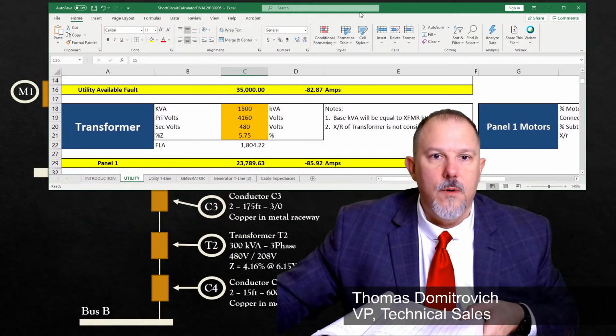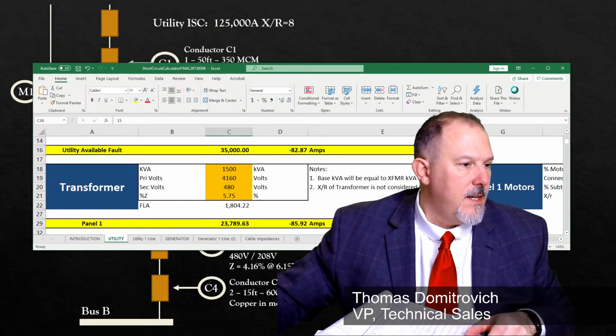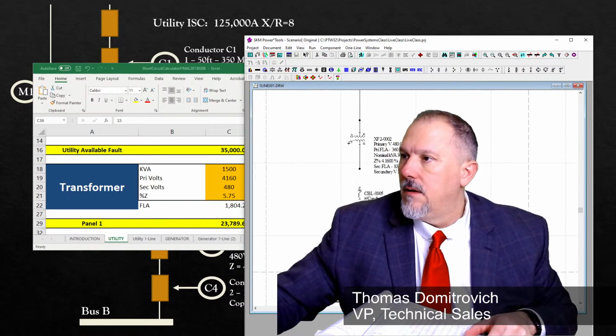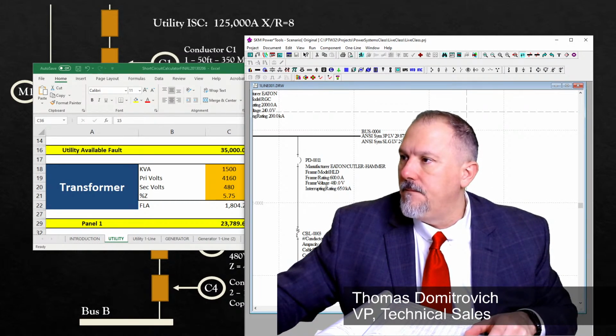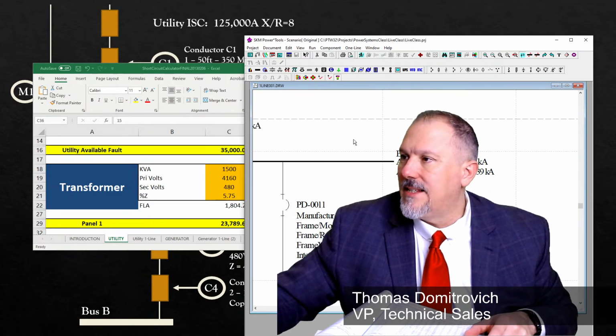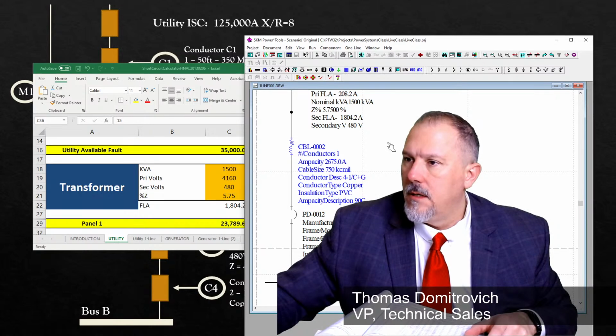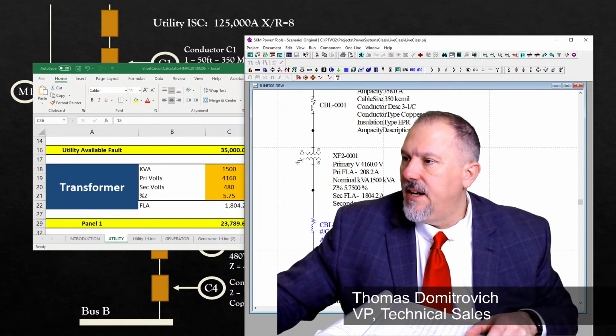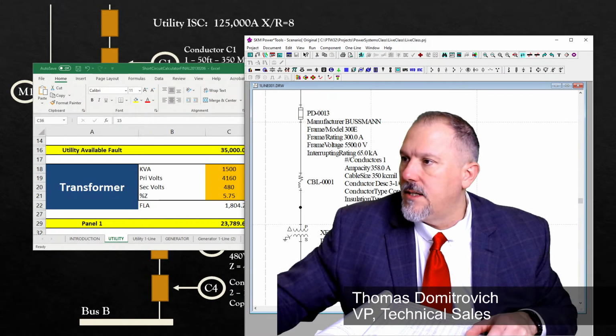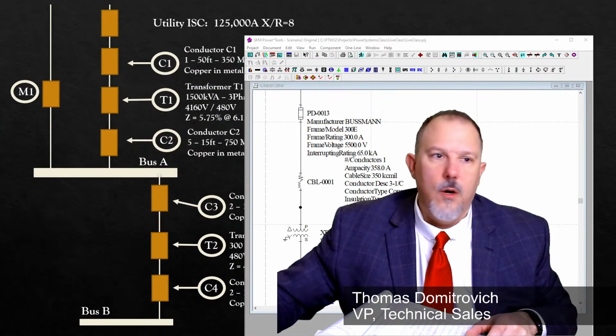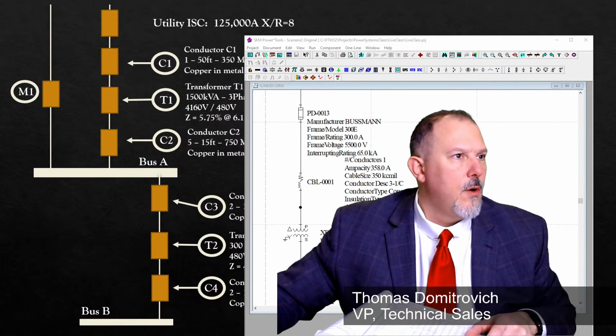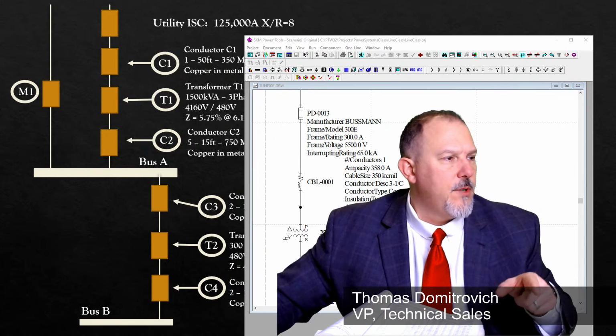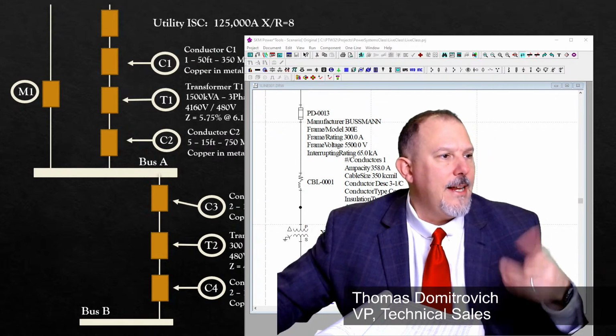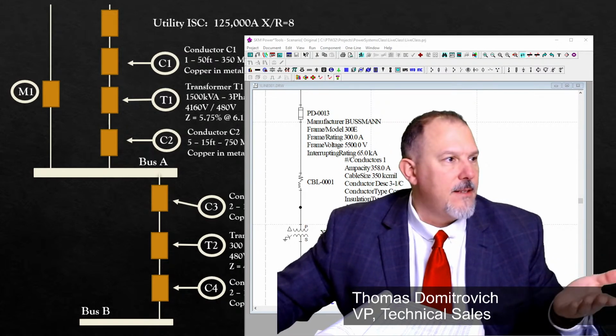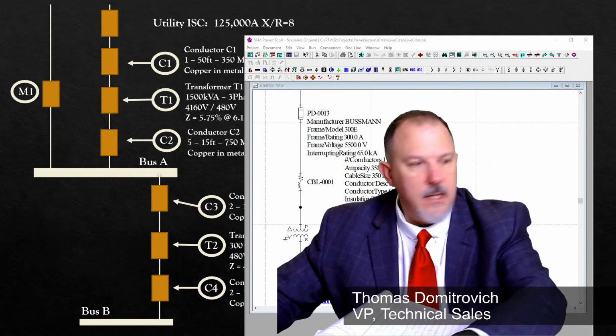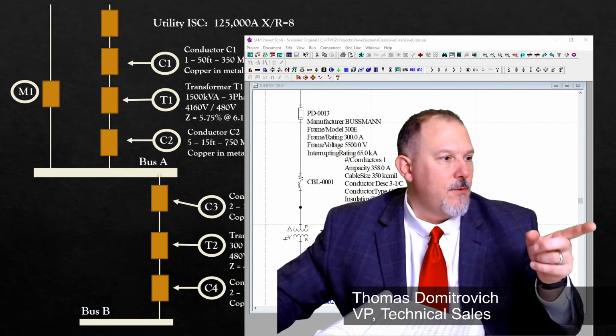23,490. What did SKM say? 23,490. We got 29,872. 5.75. 29,872. Why is that so different? Oh. So I got my transformer 5.75%, 4160 to 480. I didn't work the X to R ratio, so I didn't consider that. If I delete this, that's what it was. My fault current was really high.